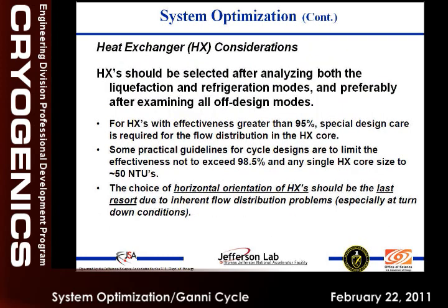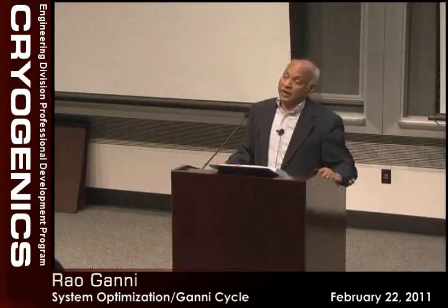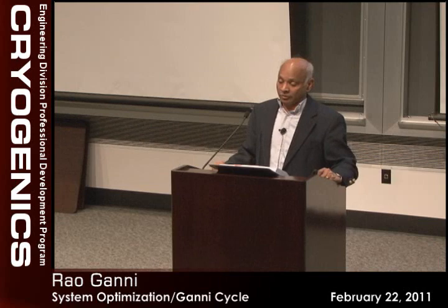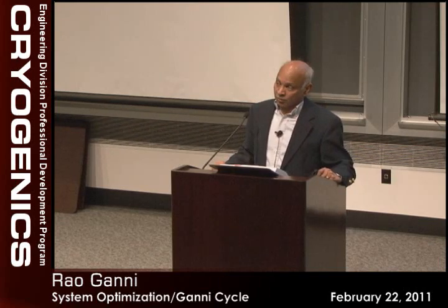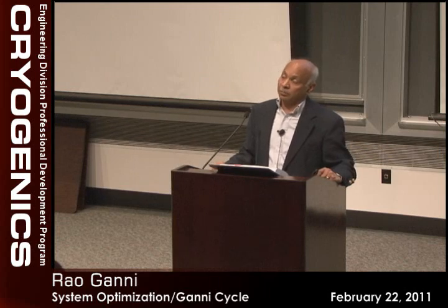Then when we come to the next component, the biggest component, we use the heat exchangers. In helium systems, we use heat exchangers of very high effectiveness, as high as 98-99%. So in process industry, where we started learning this particular area of specialty, they never pushed the heat exchange components to these high effectivenesses. And initially, at the start of my career, we didn't recognize some of these limitations. When we're pushing into 98, we used to take the same process we are using in natural gas processing industry, and we were trying to apply the same principles.